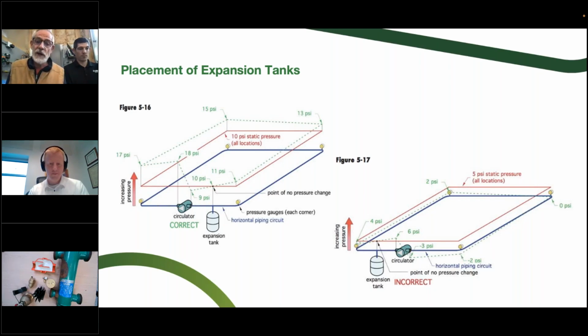So if we had an air vent anywhere from 0 down to 2 PSI or anywhere along that, what's going to happen is when that pump kicks on, every time it kicks on, you're going to get that negative pressure, and that float type of air vent will be pulled down, and you'll get a little sip of air, a little sip of air. So over the course of weeks or months, you get a call from a customer who says, the guy came over here and he purged all the air. He was here for 2 hours. He charged me. A month later, I got noise in my system again.